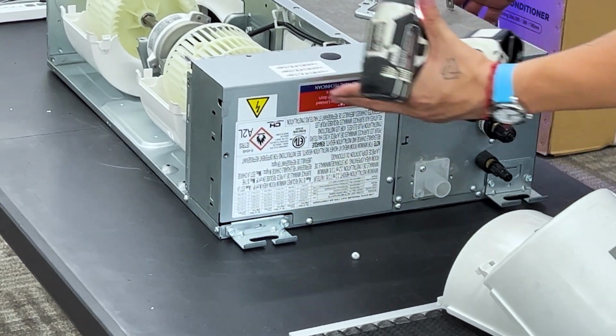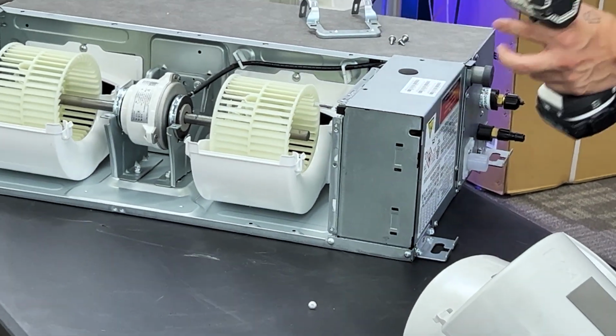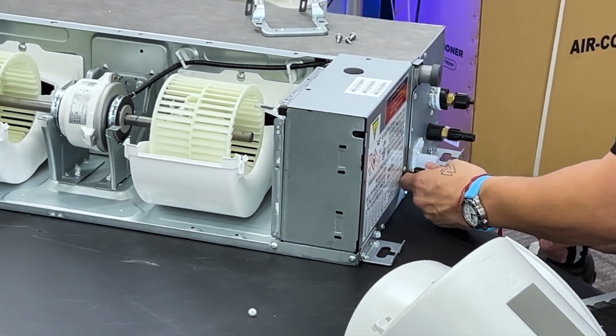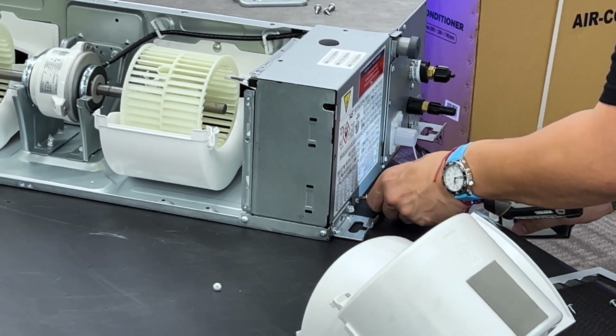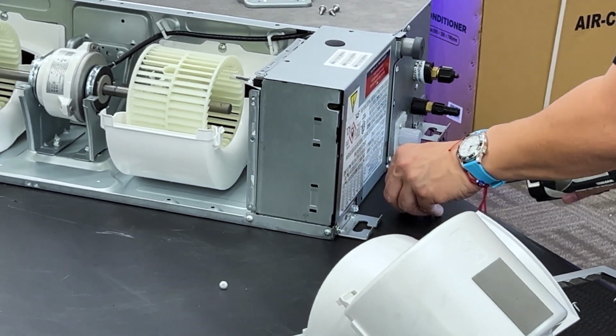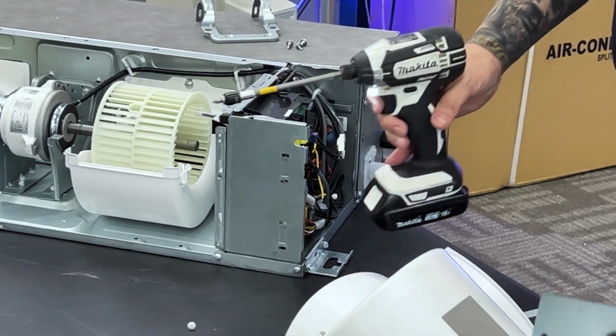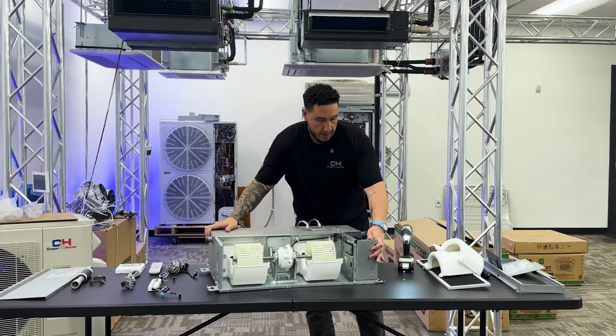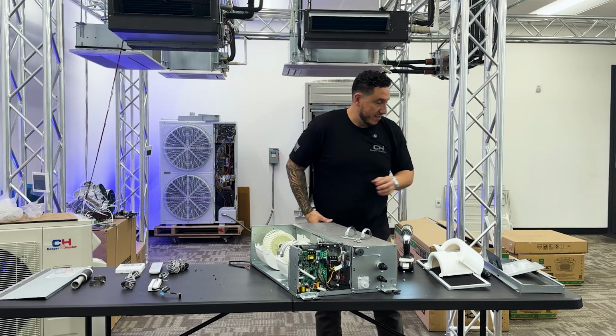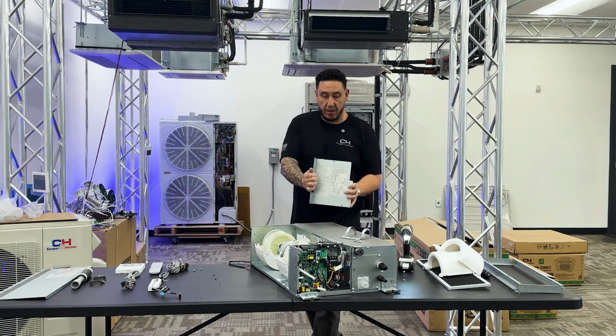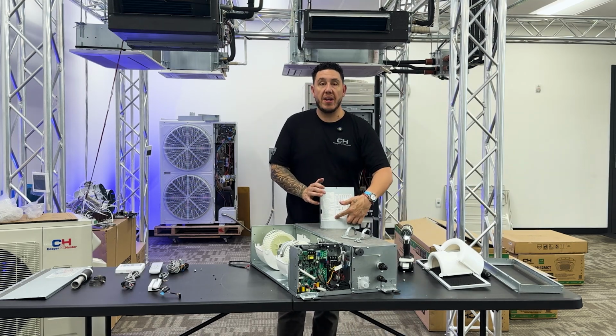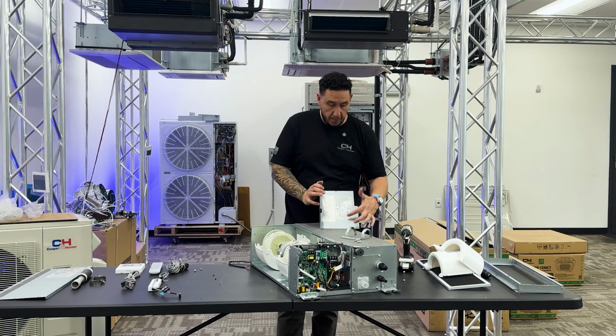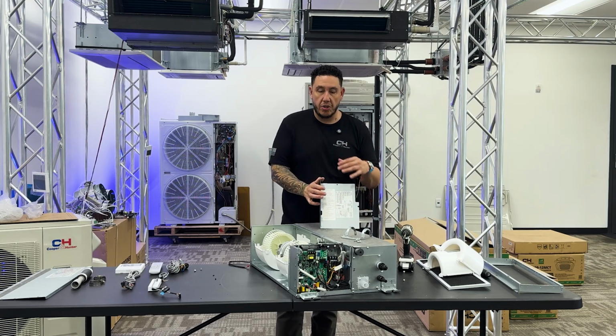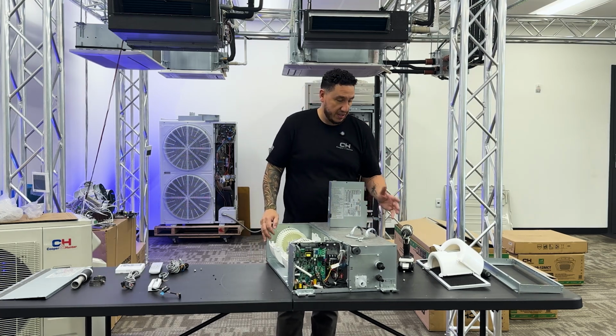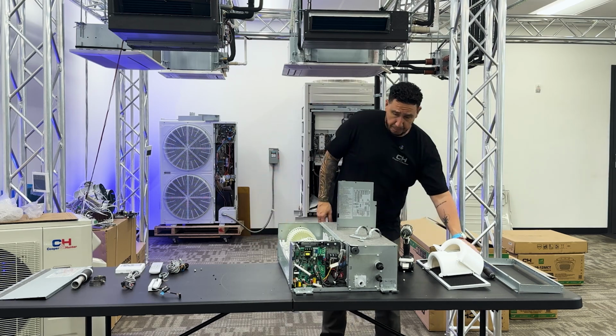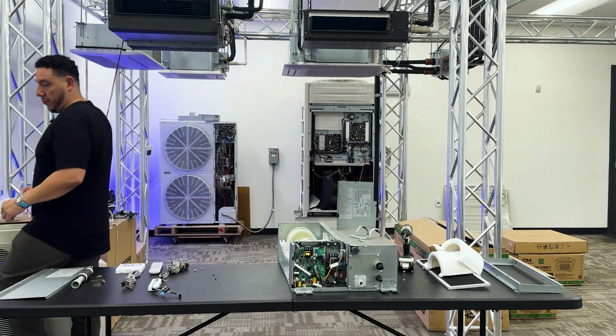So let's go ahead and remove these screws right here on the panel so I could show you everything on the main board. So it's just a couple more screws. Now we have easy access to everything there. And guys, just like all of our units, your common error codes are going to be listed on the panel. You have your dip switch settings, so you know how to change between the different sizes of this unit here, and many different connection points.